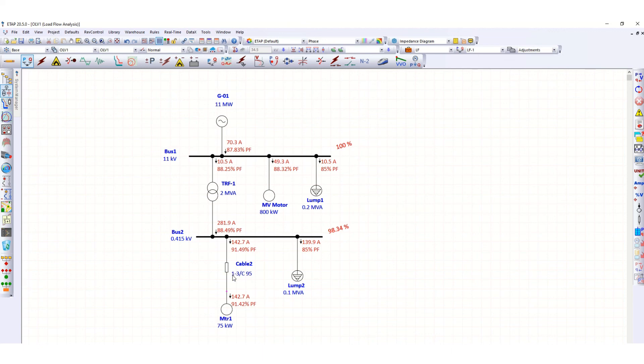This is the optimum size calculated by the ETAP software. We can use single run three core 95 square mm copper XLPE cable for this 75 kilowatt motor, which is running at 91.42 percent power factor from a 415 volt bus.